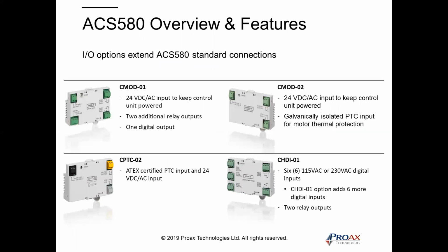In this slide, I want to talk about the option cards we offer for the 580. For example, the CMOD-01 comes with 24-volt DC, two relay outputs, one digital output. If you need more additional input/output, we have option cards that can help add IOs to your drive. The other one, CMOD-2, comes with 24-volt DC again and isolated PTC. The CPTC-02 comes with PTC and 24 volt, and another one has 6 digital inputs and 2 relay outputs. The good thing about the IO cards is they're really easy to install, and compared to competitors, easy to configure from an installation standpoint.